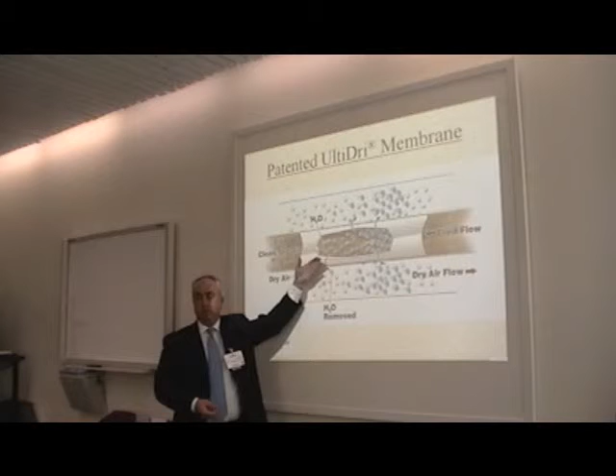That air is introduced through a series of perimeter holes on each end, sweeping down the outside of the fiber. So you have oil on the inside of the fiber and air on the outside. The differential in moisture content between the air, which has none, and the oil, which has some, is the driving force. The membrane itself is designed to be completely impermeable to oil and very permeable to water, so water molecules pass right through while oil molecules stay on the inside.